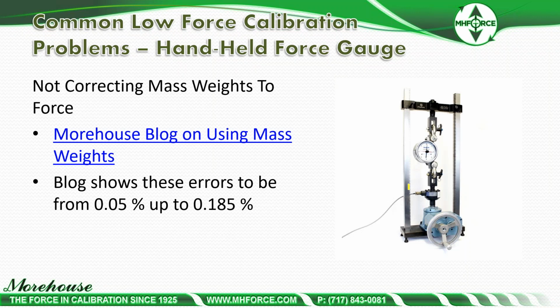We have a blog. It shows these errors are anywhere from 0.05%, which may not be a big deal, but if it's a 0.1% device, you're eating up half of the specification. Half of that accuracy, half of that tolerance being eaten up if it's 0.05%, up to 0.185%. That's in the United States. I think the worst case scenario was like PA to Alaska. I don't think I did Hawaii. These are just examples that I found with true gravities and just using mass in place of force.